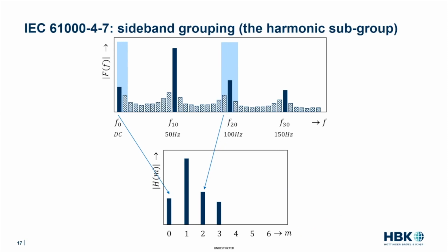Then you have the second flavor that is called sideband grouping, or in the standard it's called the harmonic subgroup. So if I first look at the second harmonic, which is in the middle of this slide, then what I'm doing is that I am generating the harmonic, so in the bottom picture, by using the energy in the 100 Hertz component, but also in the component one left of that and one right of that. So I'm combining the energy of 3 spectral components, and that forms my second harmonic. And I'm doing the same for 50 Hertz. It's not drawn here because otherwise it gets cluttered. But also to determine the first harmonic, I'm taking the 50 Hertz component and the component left and right of it. And I combine the energy, and that is the energy in my first harmonic.